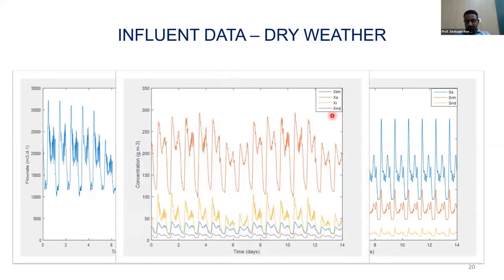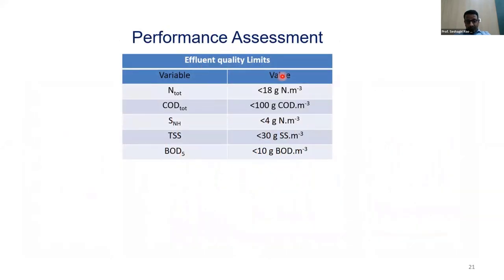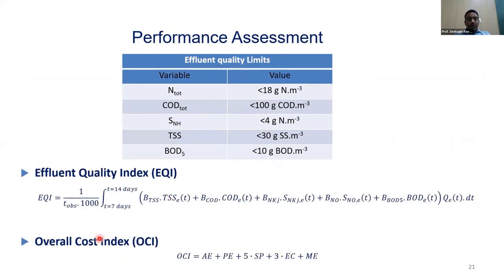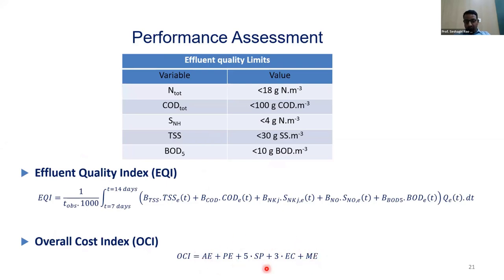Performance assessment strictly follows environmental legislation limits for COD, BOD, nitrogen, ammonia, and total suspended solids. The important metrics are the effluent quality index (EQI) and the overall cost index (OCI), which is a combination of aeration energy, pumping energy, sludge production cost, external carbon addition if applicable, and mixing energy. We determine all these energies to arrive at the overall cost index for the treatment plant.